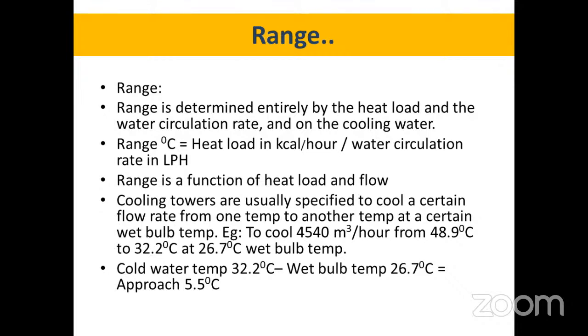Cooling towers are usually specified to cool a certain flow rate from one temperature to another temperature. Supposing there is a cooling tower, what is the rating of a cooling tower? How can we say someone has designed a cooling tower? How will they define it? By capacity. For example, a cooling tower capacity defined as: it will cool 4,540 cube per hour from 48.9 degrees centigrade to 32.2 degrees centigrade at a wet bulb temperature of 26.7. We can see the cooling rating of that cooling tower.